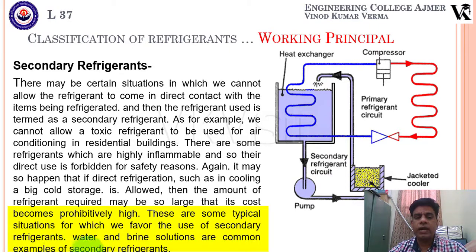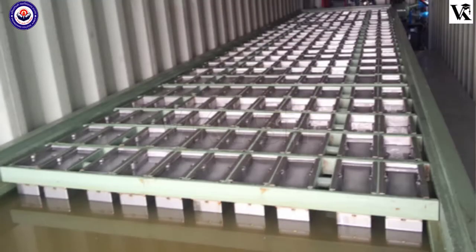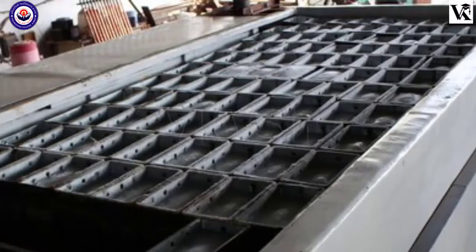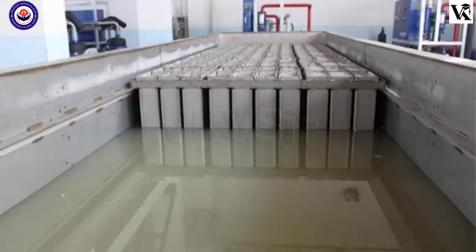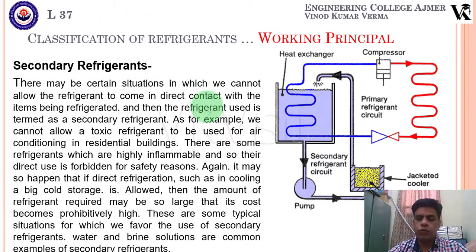Water and brine solutions are common examples of secondary refrigerants. In ice factories, for example, a brine solution is used. Adding salt to water lowers its freezing point to around minus 4 or minus 5 degrees. The primary refrigerant does its cycle, and the brine solution works on the ice. If there is a leakage, the brine solution comes into contact — not the poisonous primary refrigerant. This is why we use secondary refrigerants.